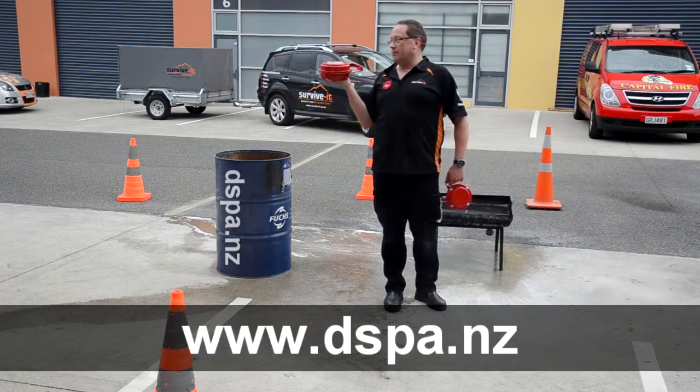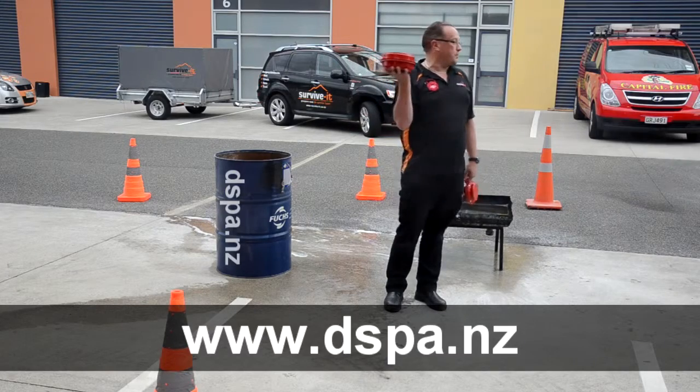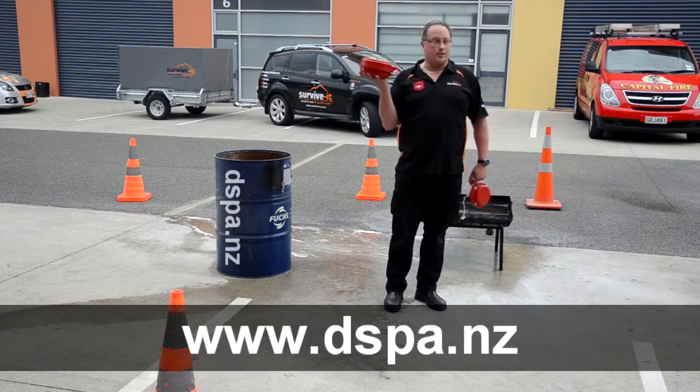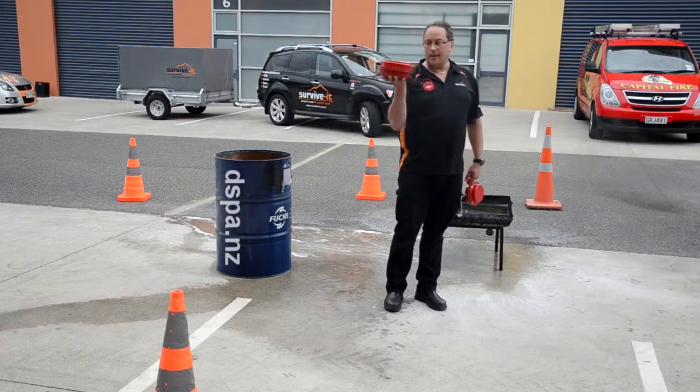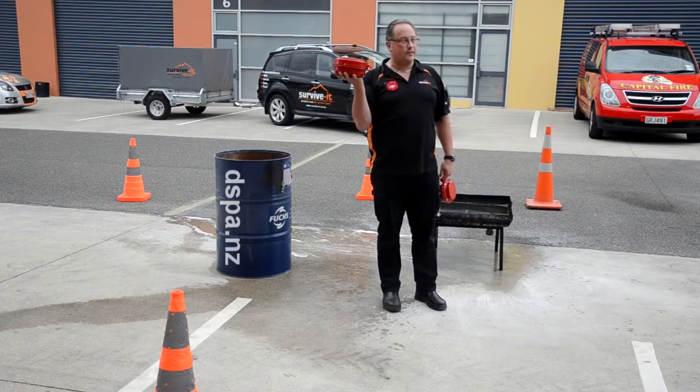These things work under water. This one here in my hand will do up to 165 cubic metres — pretty much the size of our warehouse. This could go off and potentially put the fire out. They have a failsafe built in, as they will self-activate at 300 degrees.